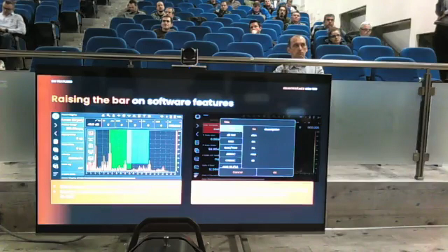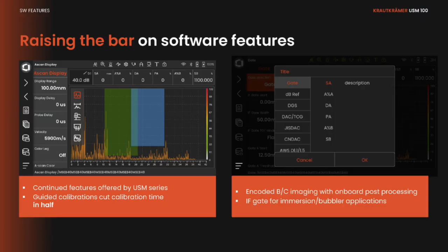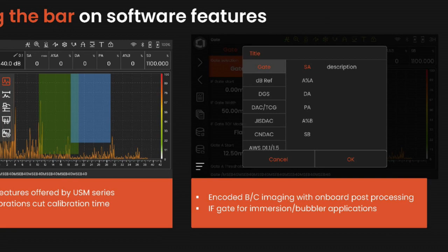One of the new features on this device, and it's quite important for us, is the ability to do encoded B-scan and C-scan imaging. We had similar technology on our Mentor UT, our entry-level phased array system for corrosion mapping, but we've now brought that technology into the conventional device. We can touch on that later on.